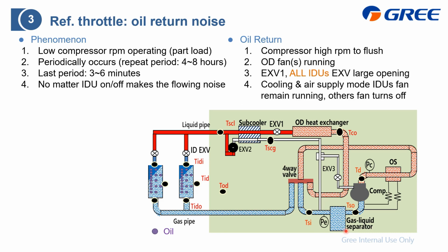And how to do it is that we raise the compressor RPM to apply a high refrigerant flow rate to push or flush this oil back to here. So in the oil return period, the outdoor fan is still operating. The outdoor unit EXV, this EXV1, is fully open. You can consider this oil return to be like defrost or cooling, either is fine. But the indoor unit EXV, either on or off, will open. Do you know why we need this one?